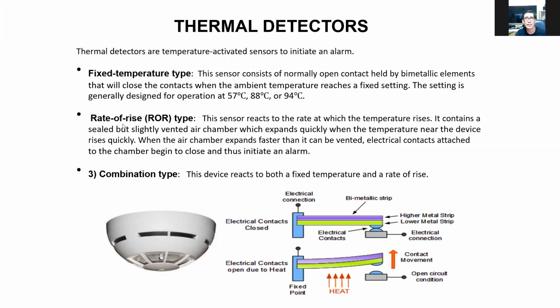Now the rate of rise type. The sensor reacts when the temperature rises. It contains a sealed but slightly vented air chamber which expands quickly when the temperature near the device rises quickly. When the air chamber expands faster than it can be vented, contacts attached to the chamber may close and initiate an alarm. Now we have the combination of the two, the fixed and the rate of rise type.